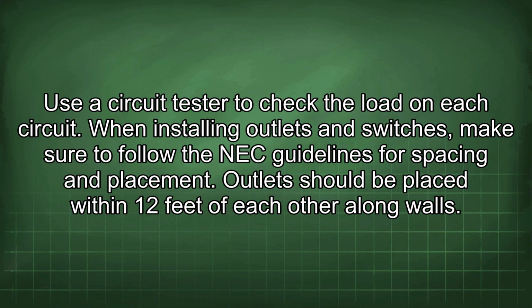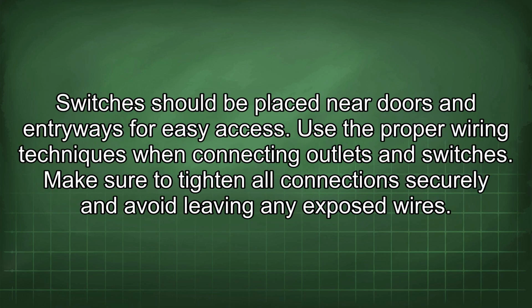When installing outlets and switches, make sure to follow the NEC guidelines for spacing and placement. Outlets should be placed within 12 feet of each other along walls. Switches should be placed near doors and entryways for easy access. Use the proper wiring techniques when connecting outlets and switches. Make sure to tighten all connections securely and avoid leaving any exposed wires.